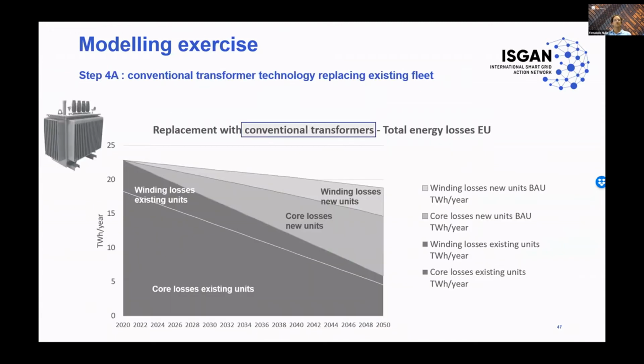So what happens in the first scenario, which is conventional transformers replacing the existing fleet? So the existing fleet goes here. There is a share between core losses and winding losses. And the new fleet is in the lighter color, also with core losses and winding losses. So this is the way losses evolve. Despite the increase of loads, losses reduced because of the eco-design regulation requiring more efficient units. So overall, losses would reduce.